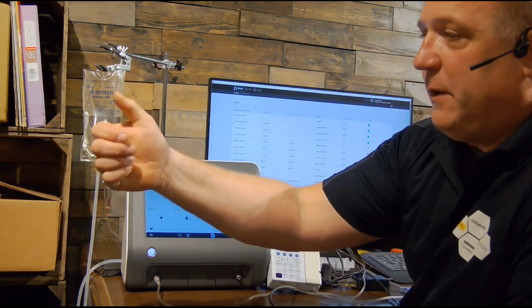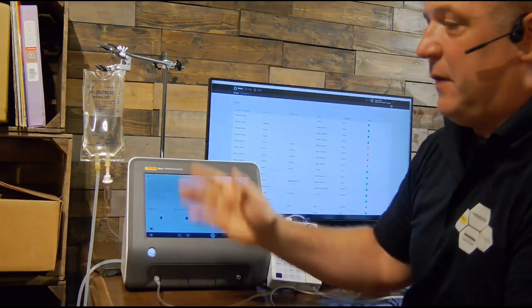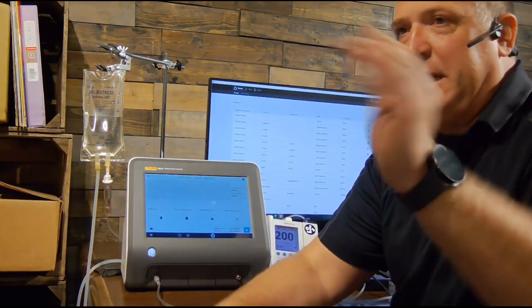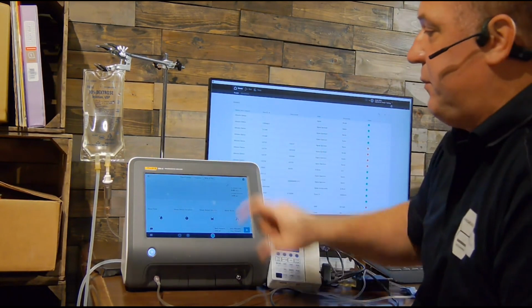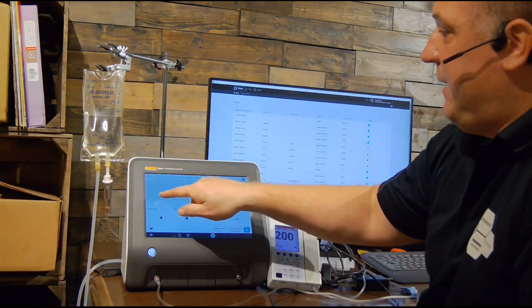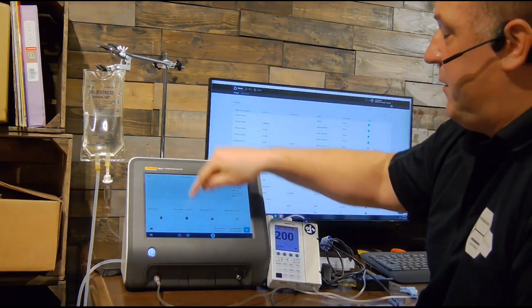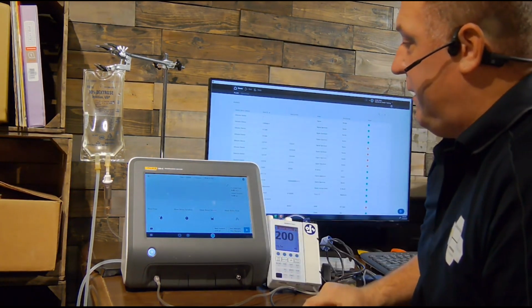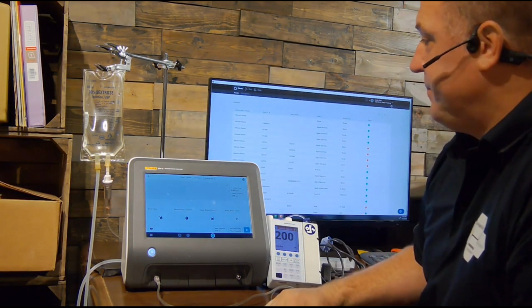So then you can do 3, 4, 5, 6, 10, 15 of those, and it's going to average them together. So you can get rid of the high and the low and get good bolus readings on it. And you'll actually see a baseline with your square boluses. So that's a really, really nice feature, and it does it very accurately here.